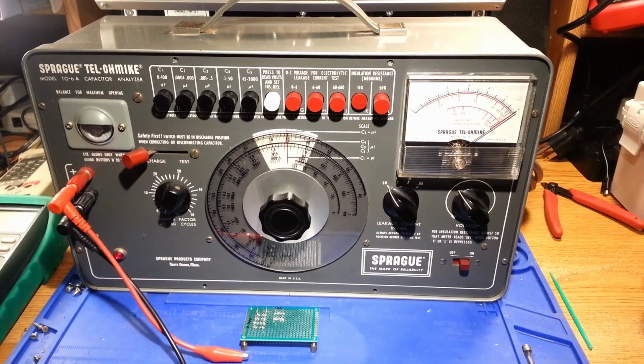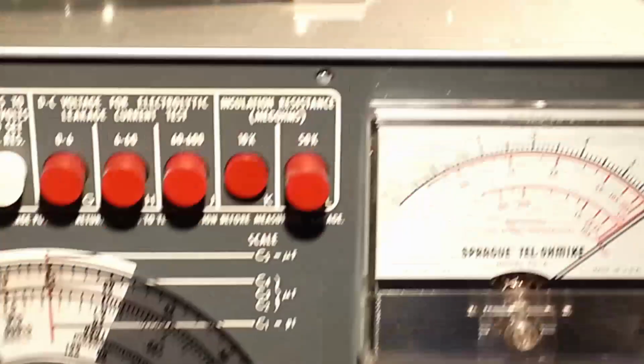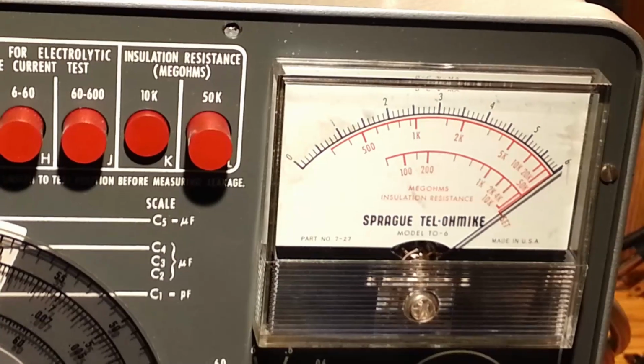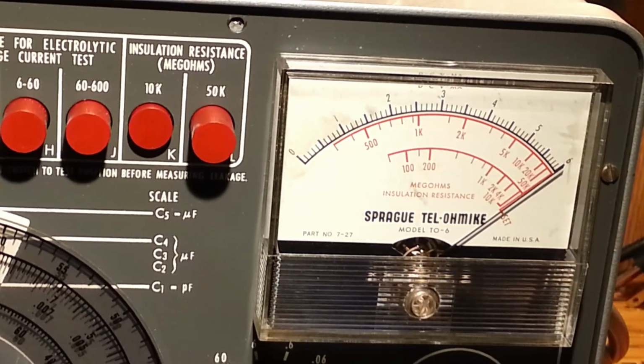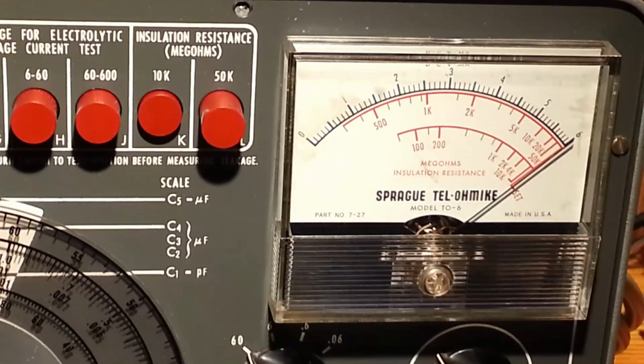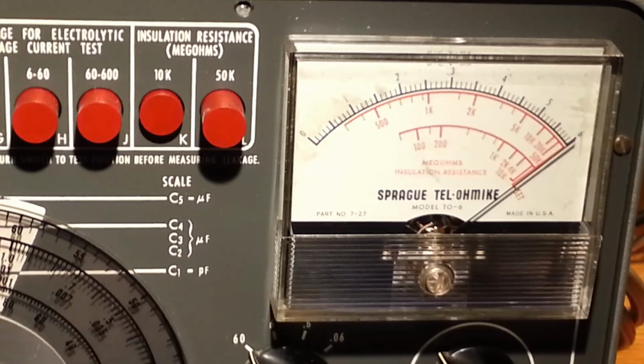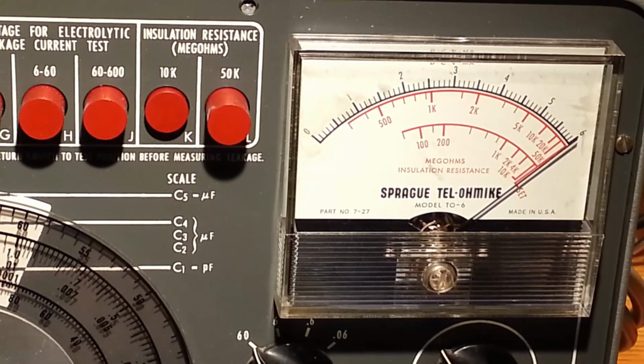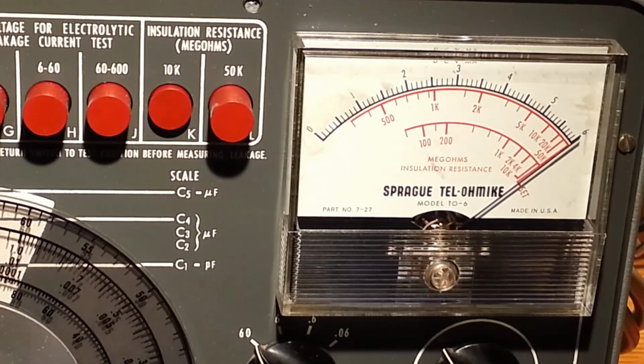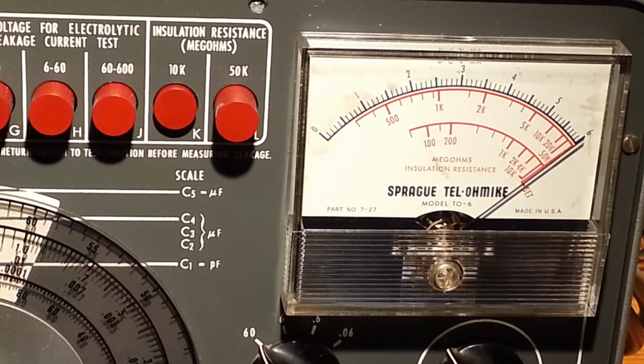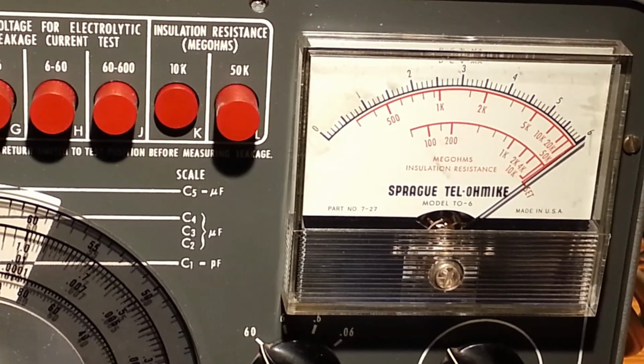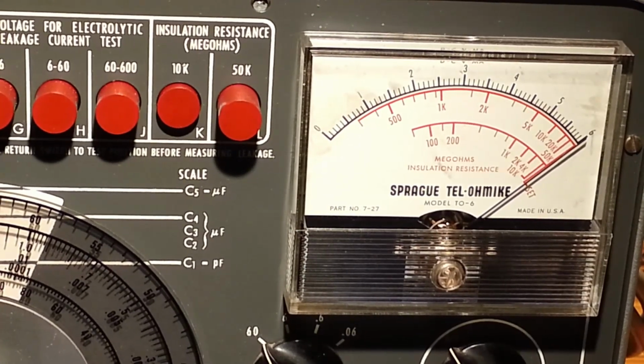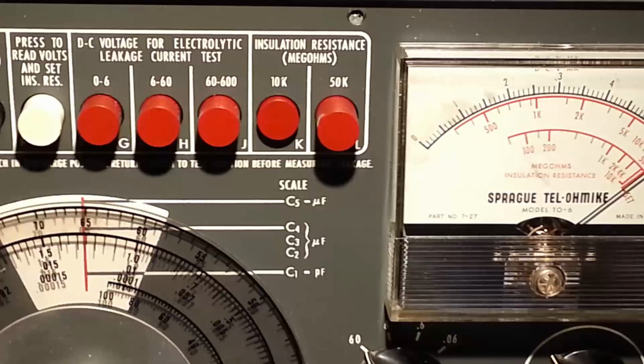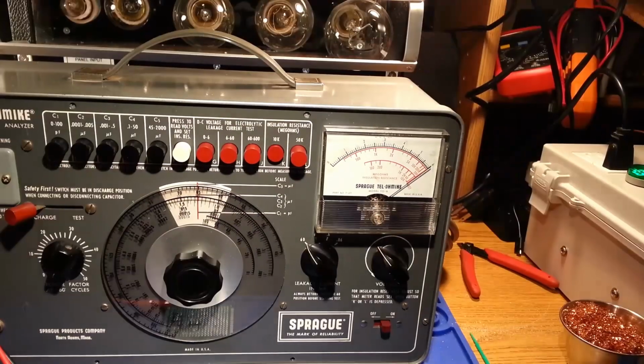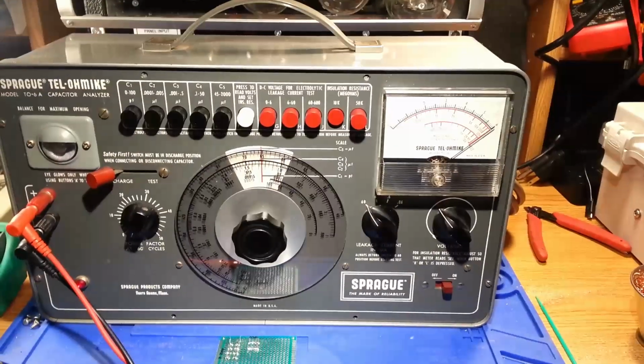It has a function on it called insulation resistance. You can see the two buttons on the top there. The first is marked for megaohms, and the first button is marked as 10K, so it would be 10 kilo megaohms or 10 gigaohms. Second button range is 50K or 50 kilo megaohms or 50 gigaohms. So what I'm going to do is check and see if it's actually functional for that.